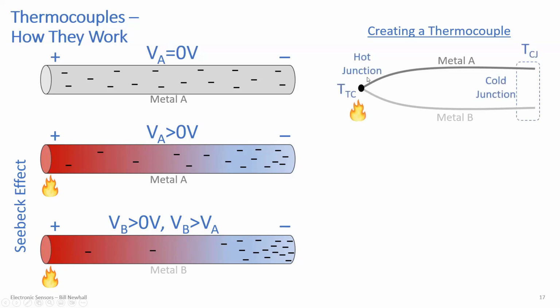That left side is generally called the hot junction, usually where you're measuring something hot, and it's defined to have the temperature T sub TC, the thermocouple temperature. On the other side, where it's cold, we call that the cold junction, with temperature T sub CJ. We've caused these voltages to happen because of the Seebeck effect across each metal, and since metal A and metal B have different voltages from end to end, we get this voltage across the cold junction.